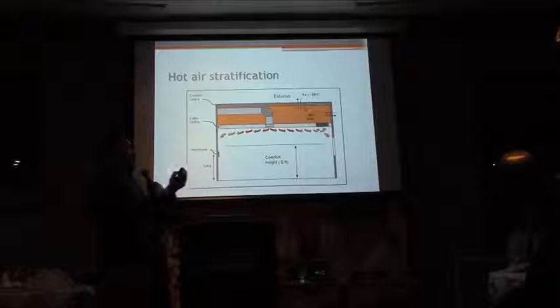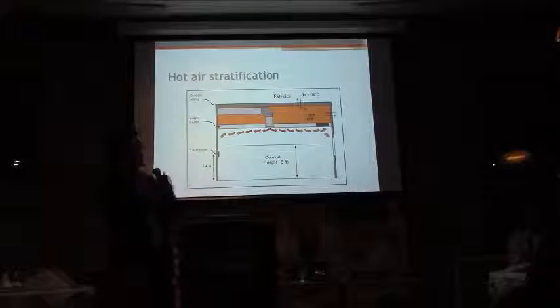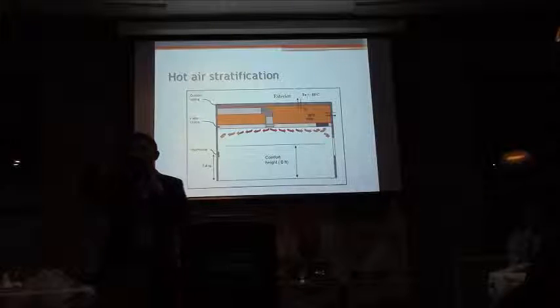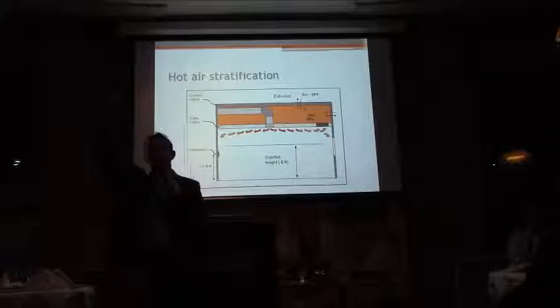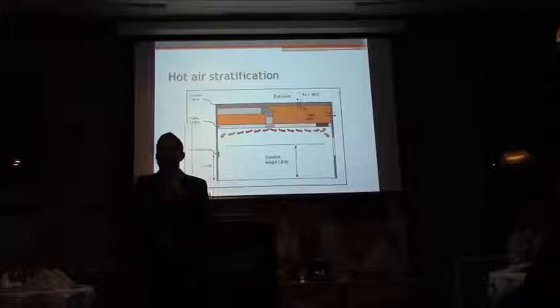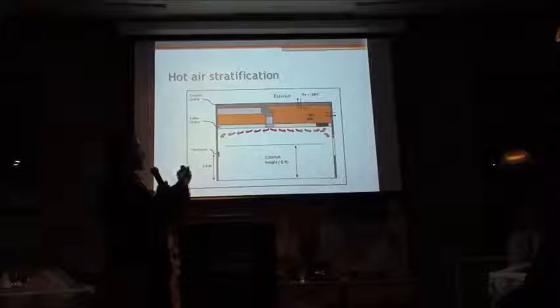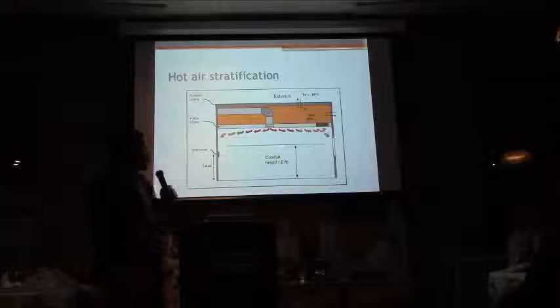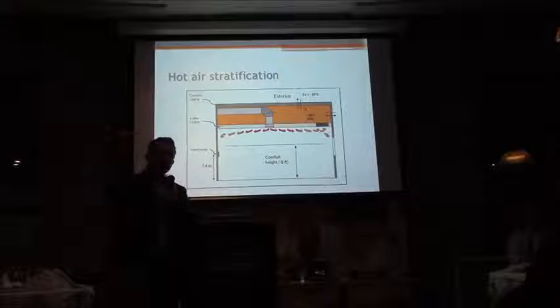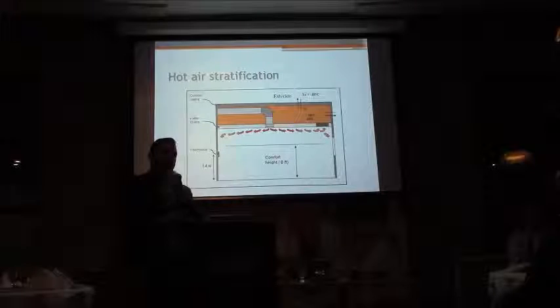So when you do that, it poses a challenge for ventilation, because you're going to diffuse your hot air from the diffuser in the ceiling, you're going to return from the ceiling, and hot air has this tendency to just stay high, because it has a lower density. It doesn't naturally come down into the occupied zone like cool air does. So it poses a challenge for ventilation if you want to supply hot air and return through the ceiling. So to avoid that, you need a diffuser that's going to give enough velocity, enough vertical push, for all that hot air to reach the occupied zone.